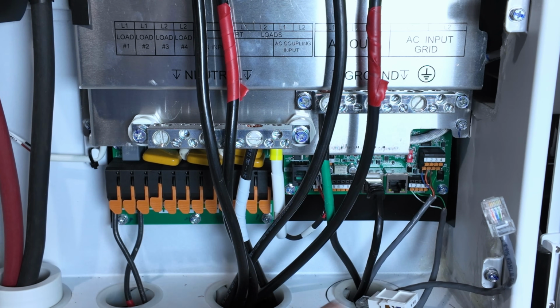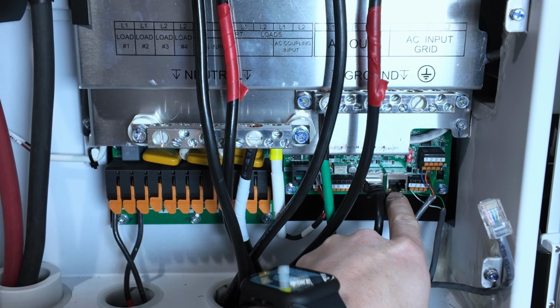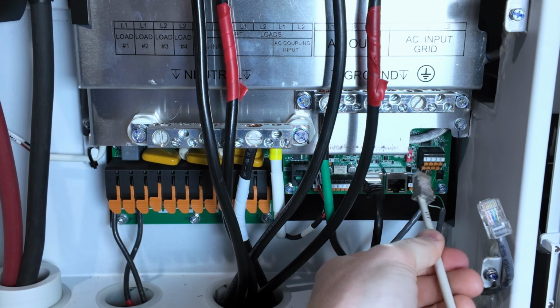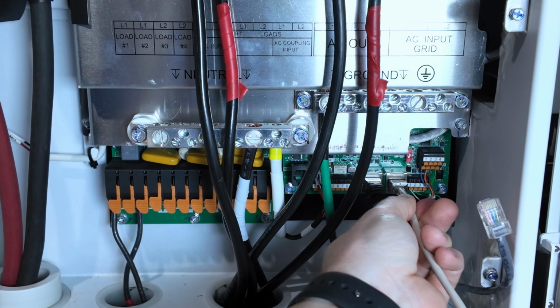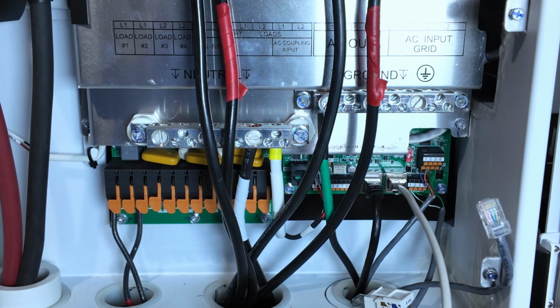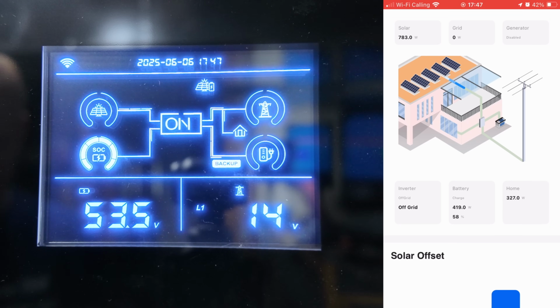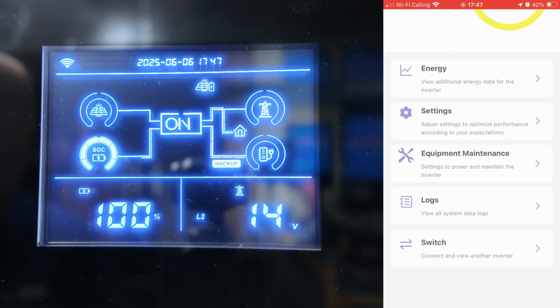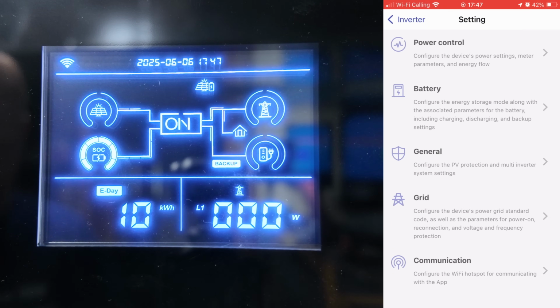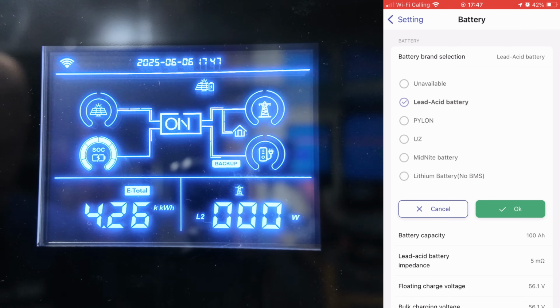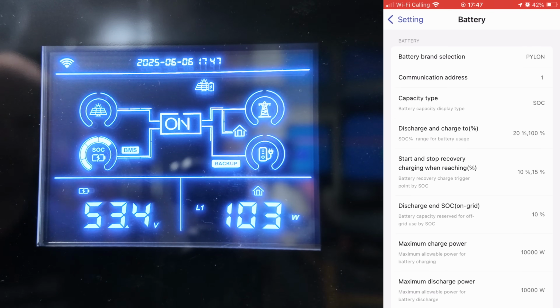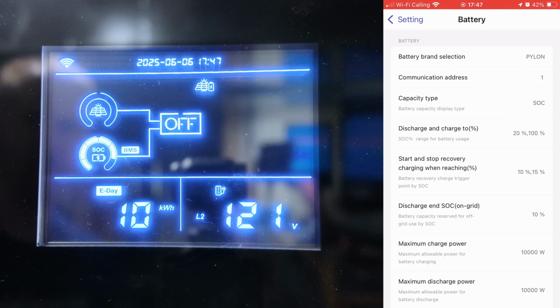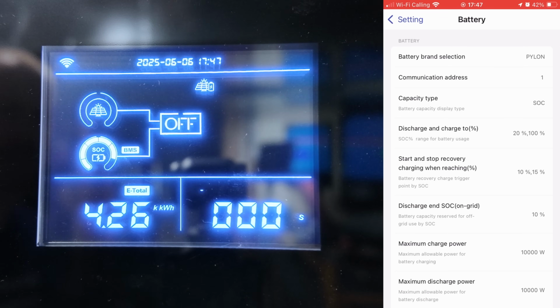On your MidNite inverter, you're going to run a cable over to this port right here, which is your BMS communication port. I actually have to add an extension onto mine so that it'll reach. So you'll come into your MidNite app, go to settings, battery brand, set it to pylon, hit OK, and it will update with your battery information.